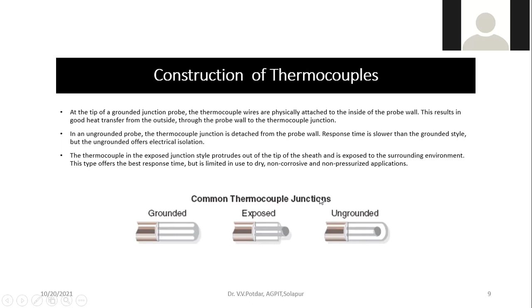So use of exposed junction type thermocouple is limited to dry conditions, non-corrosive environment, and non-pressurized applications, right? Otherwise, for general cases, grounded is best. Next is ungrounded, and last choice is exposed. Okay, this is the broad categorization of thermocouples.